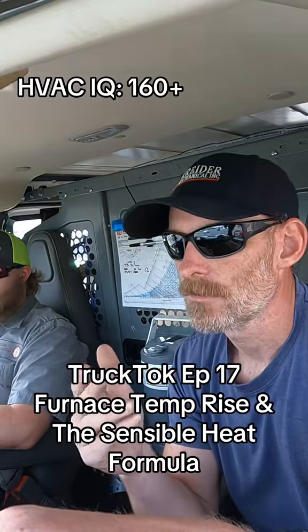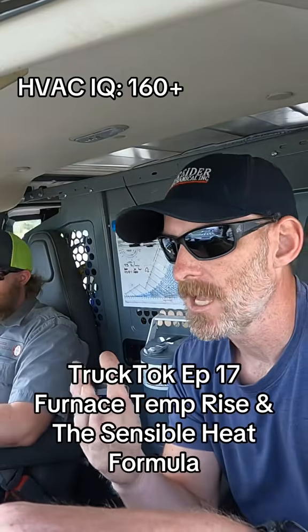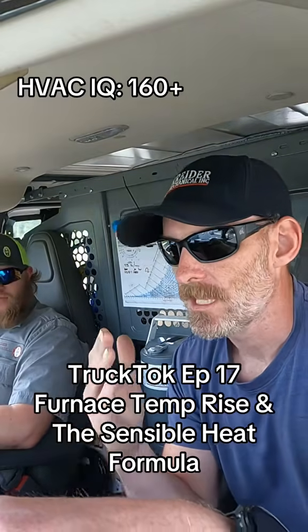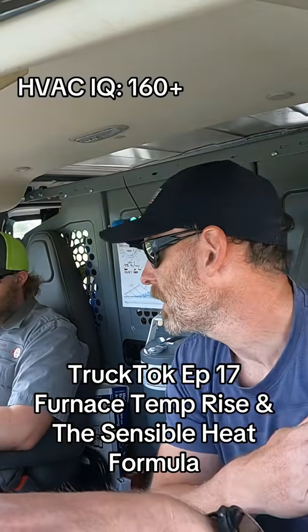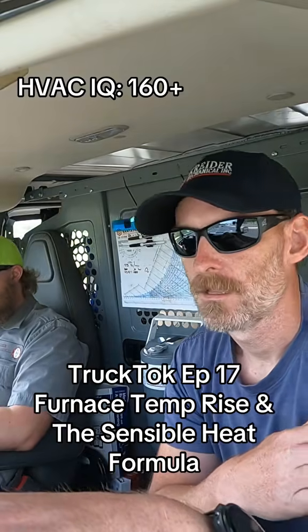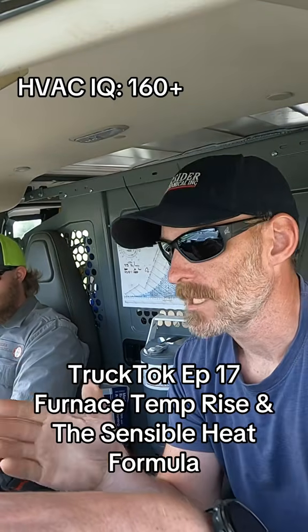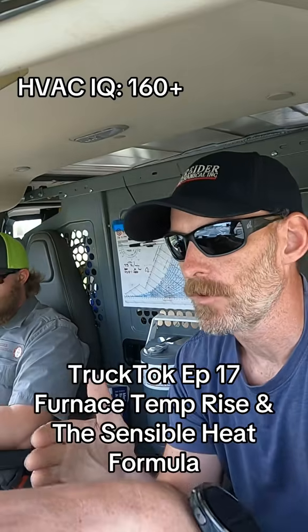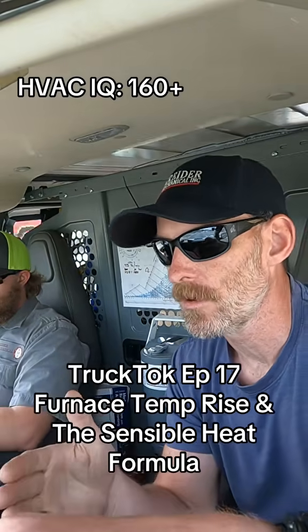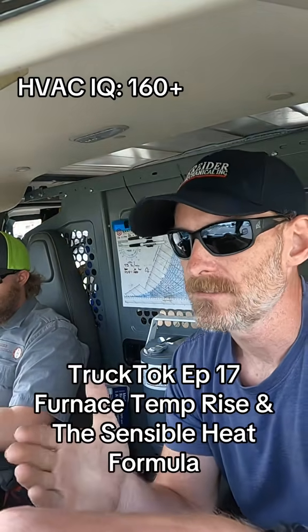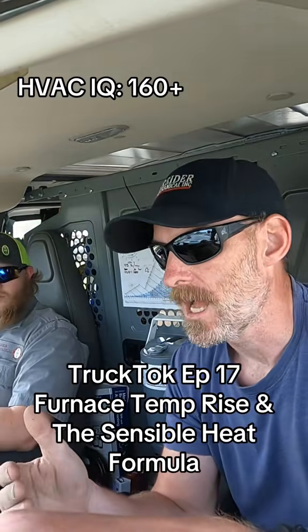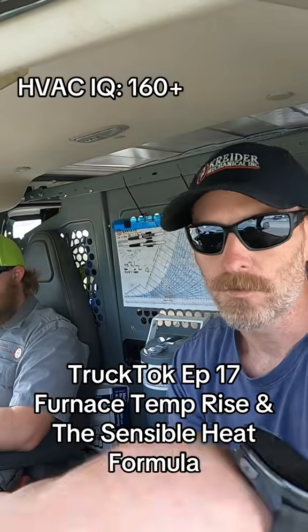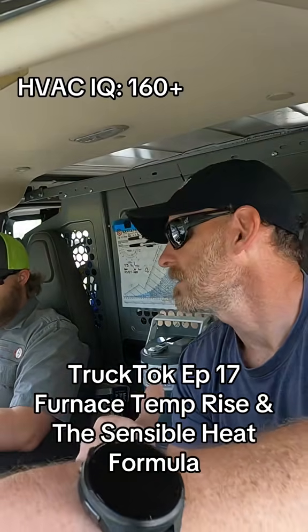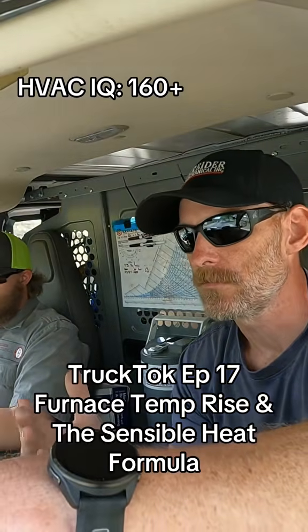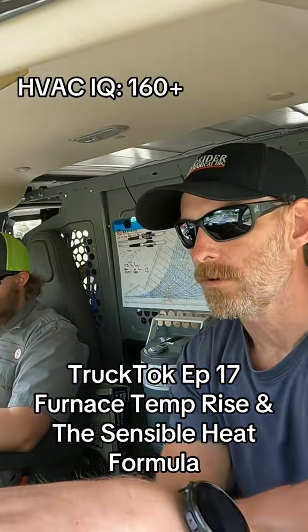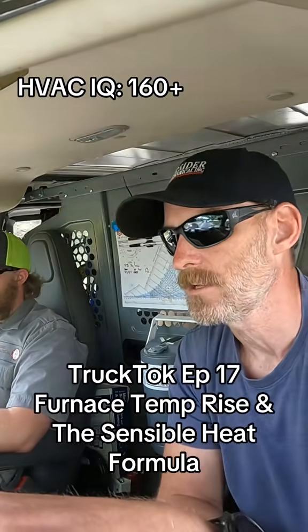Correct, if it's too high or too low. They want you to be able to provide enough air that can handle the heat that's being created by that heat exchanger, right? Yes. Okay, so if everything else was normal, like your inlet pressure and your manifold pressure and your combustion numbers were all good, but you had a high temp rise, you probably also have a higher flue temp, wouldn't you? Yes.